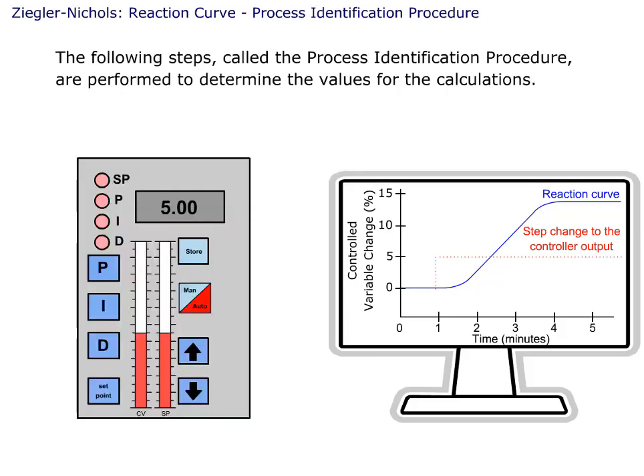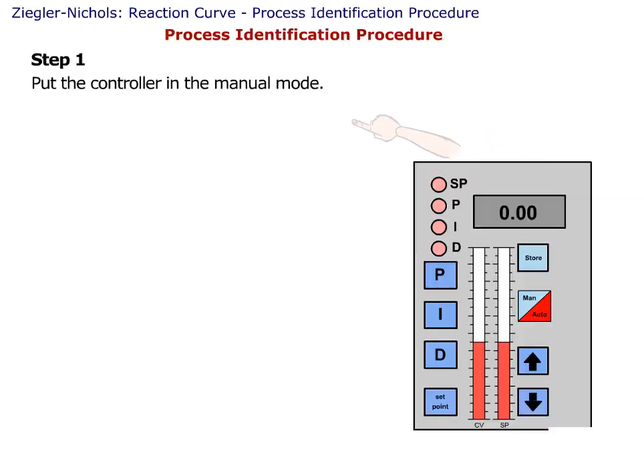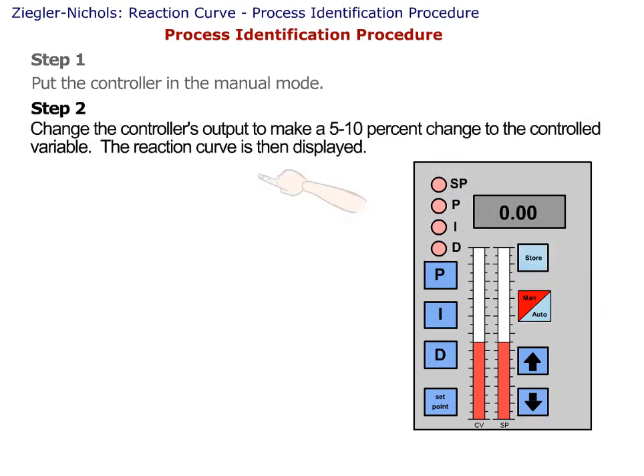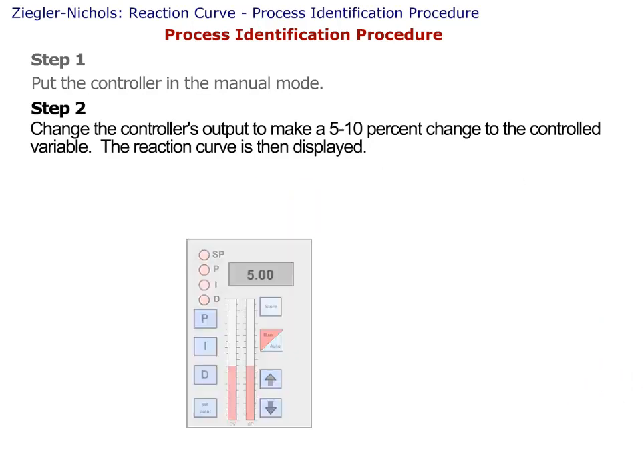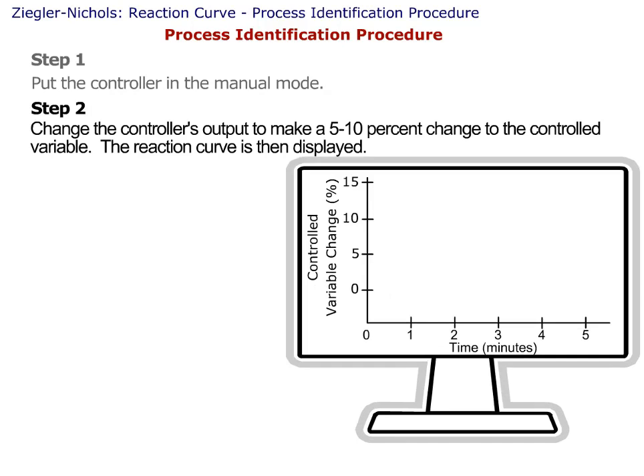The following steps, called the process identification procedure, are performed to determine the values for the calculations. Step 1: Put the controller in the manual mode. Step 2: Change the controller's output to make a 5 to 10 percent change to the controlled variable. The reaction curve is then displayed.